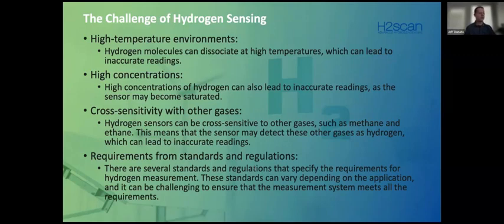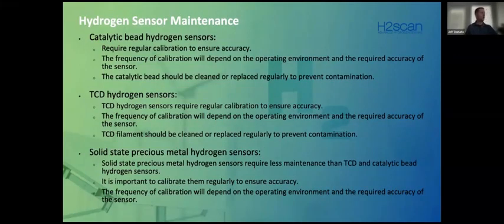Again, with the ventilation standards, sometimes you can prove that you have it covered with your ventilation system, then you may not be required to put detection in. But if you're not necessarily meeting all of those cases when it comes to float or boost charge, then the AHJ may choose to have the detection put in to cover any kind of worst case scenarios. And there are different kinds of sensors and different maintenance that goes along with those.